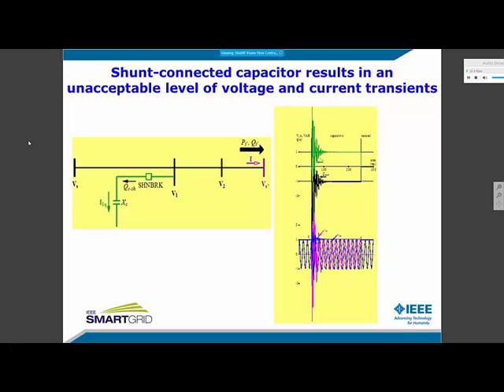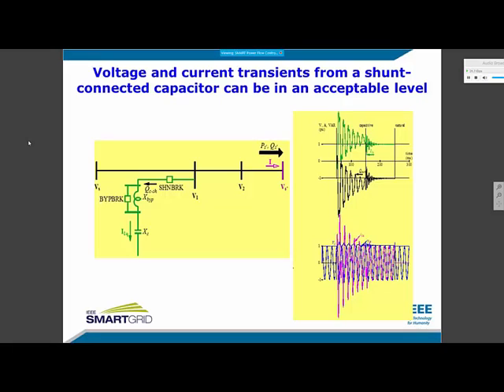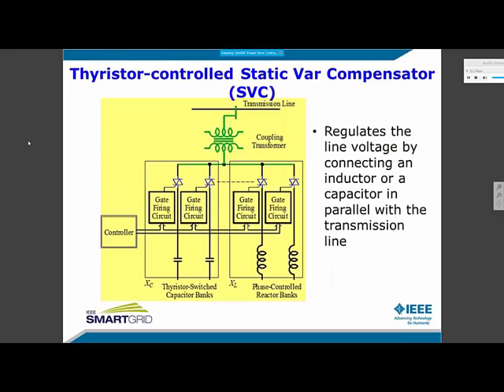A shunt-connected capacitor may result in an unacceptable level of voltage and current transients, which can be mitigated, as shown in this picture. Voltage and current transients from a shunt-connected capacitor can be at an acceptable level if a series inductor is used with the capacitor. This inductor may be bypassed after the initial transients are over.